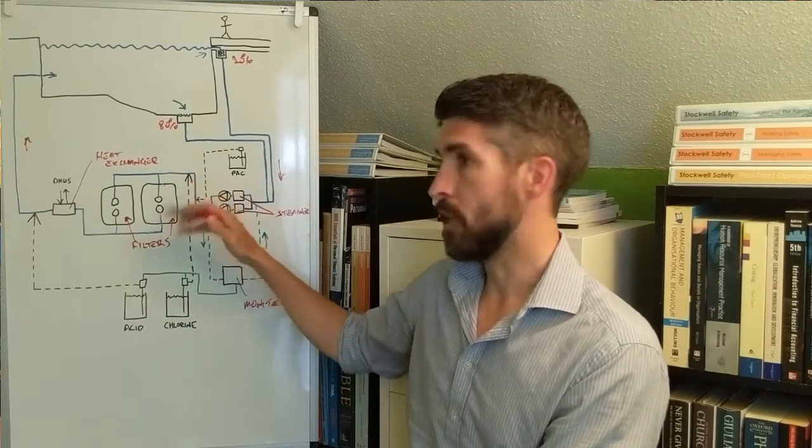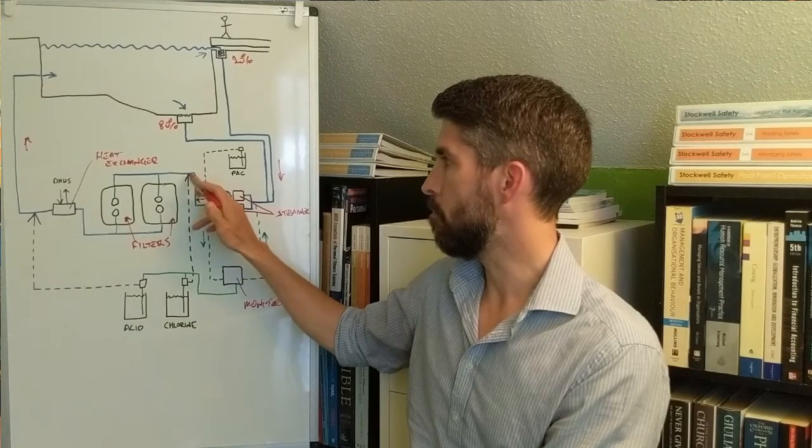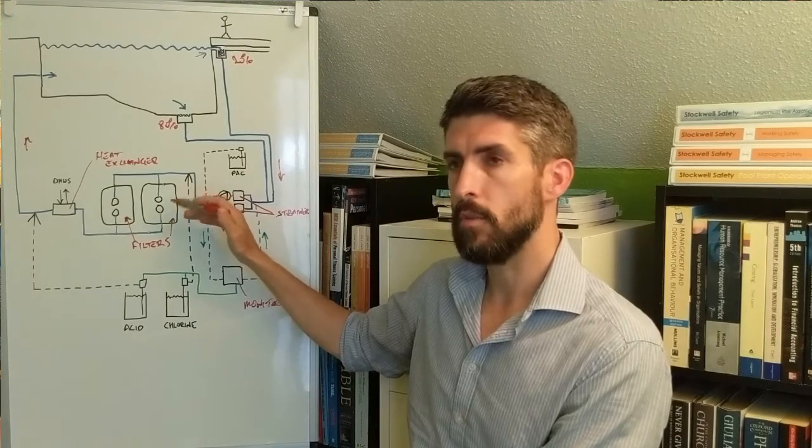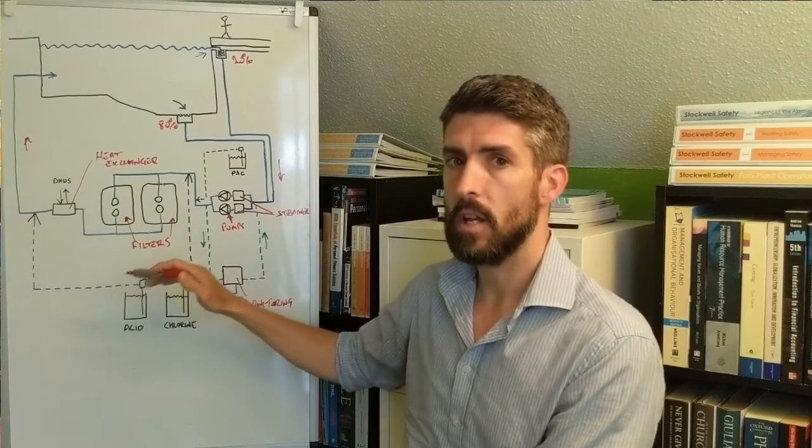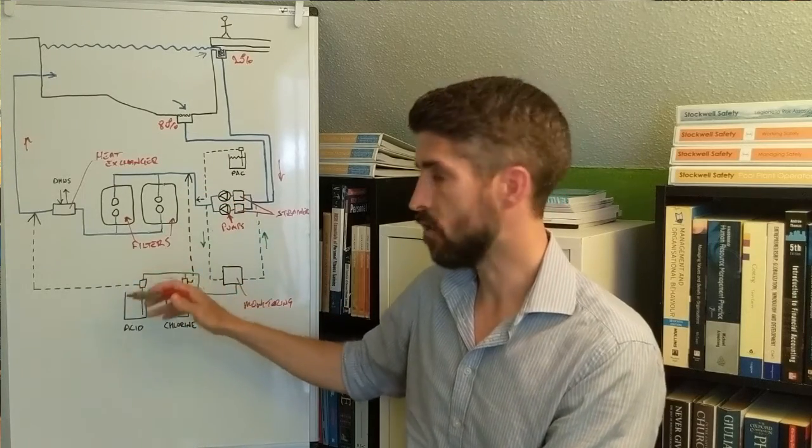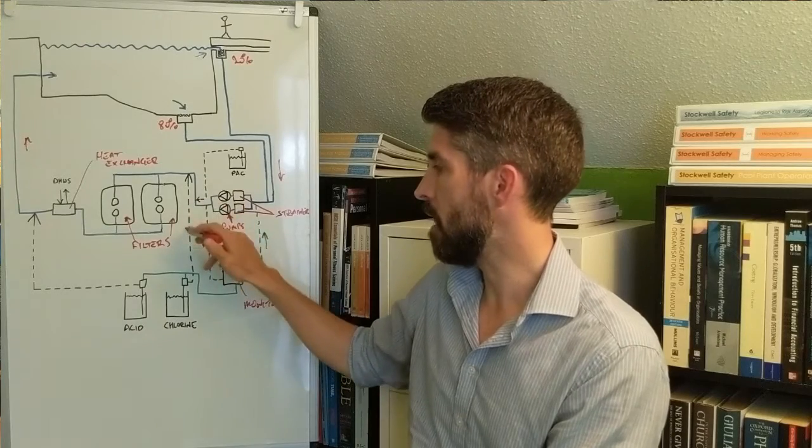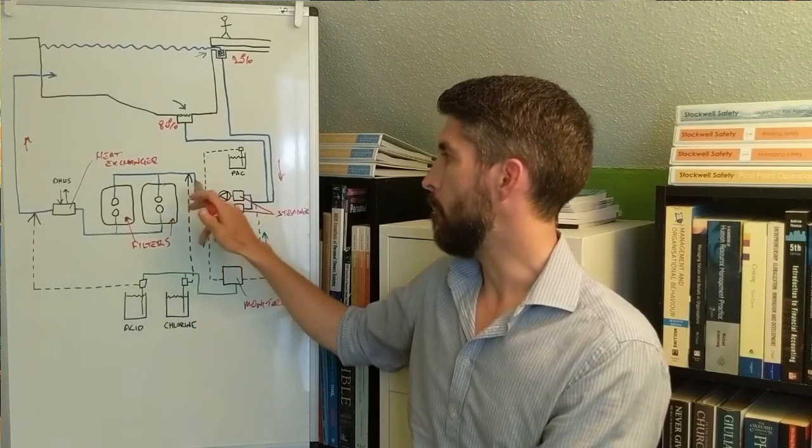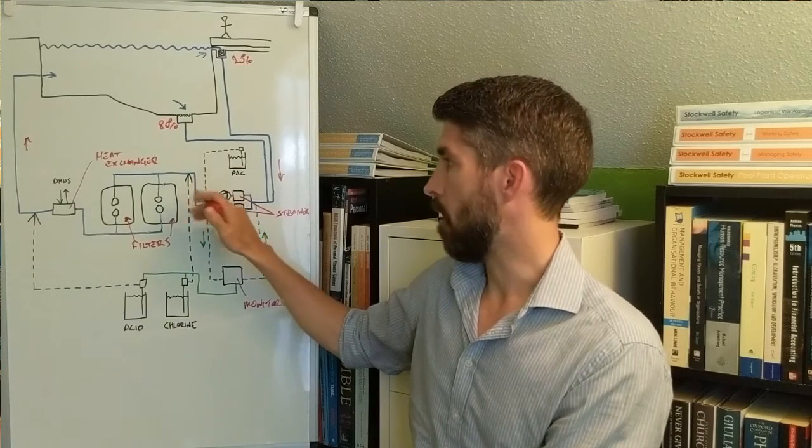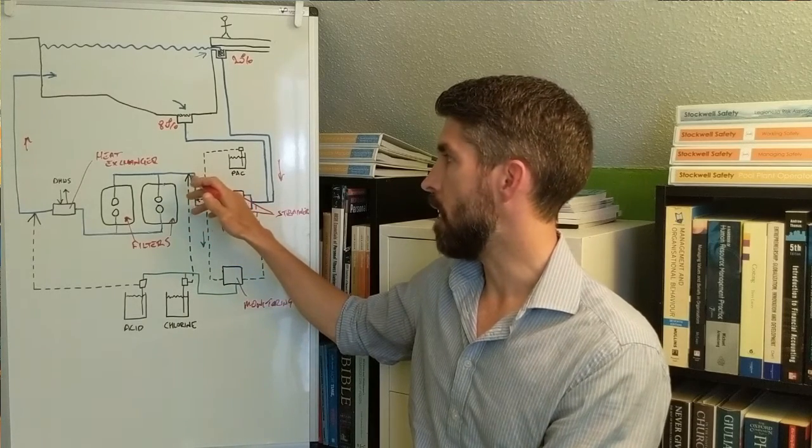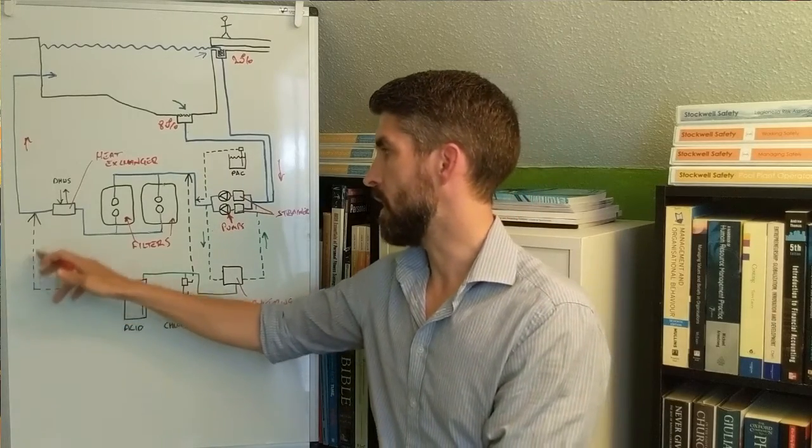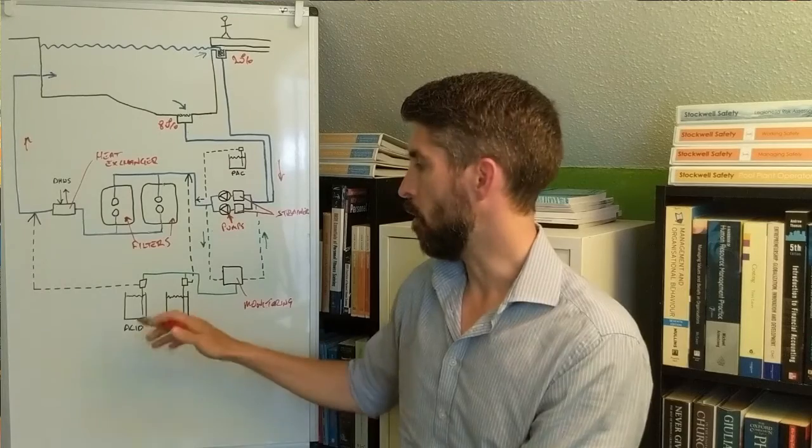The chlorine here on this particular example is being dosed pre-filter. That's not always the case. In some plant rooms you might find the chlorine being dosed post-filter, downstream of the filter. So there's a bit of variability to where the chlorine is injected. But on this particular example, I've got the chlorine being dosed in before the filters.